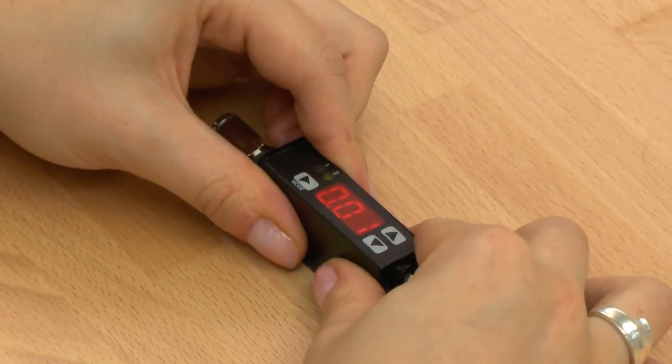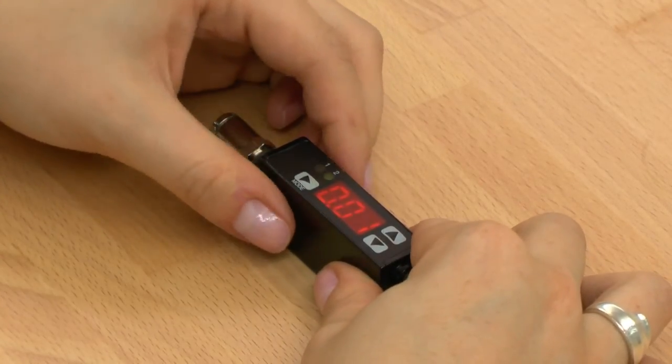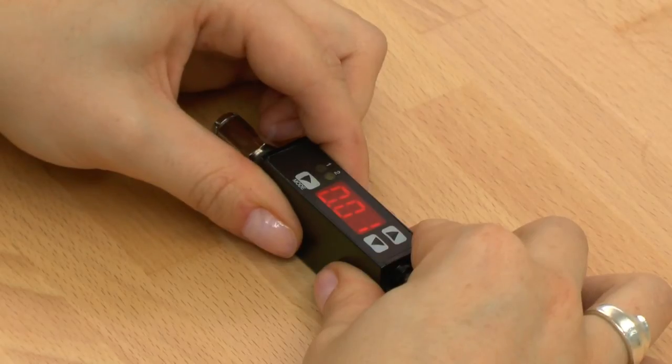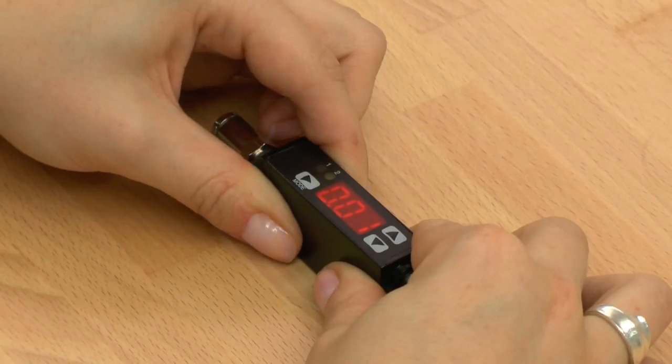Now we can adjust the operating modes. The VSVD can be operated in 2 different operating modes. Each output can be adjusted to one of the operating modes independently. Hysteresis mode settings are switching point H and hysteresis little h. Comparator mode settings are lower margin A and upper margin B.